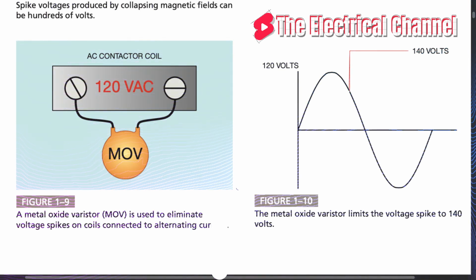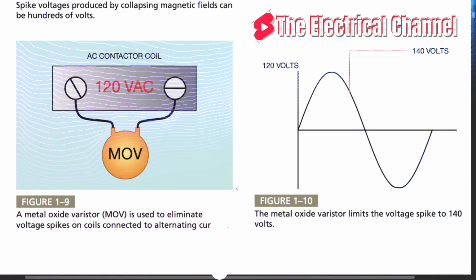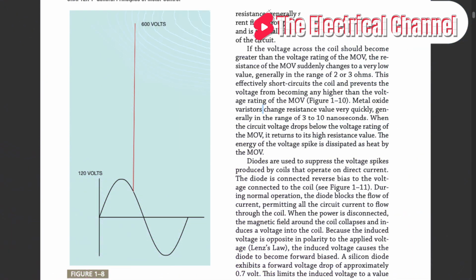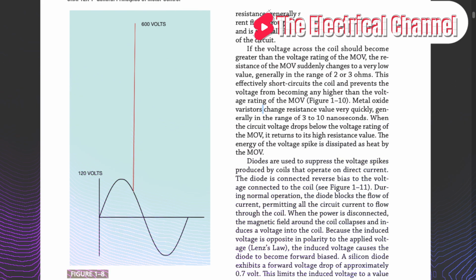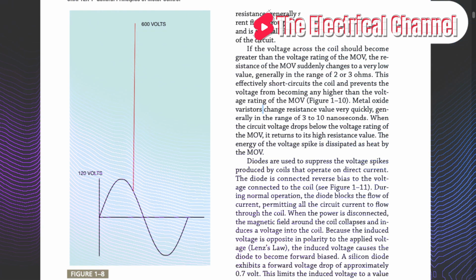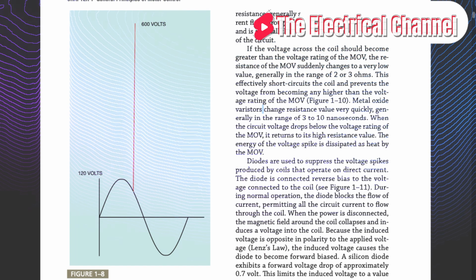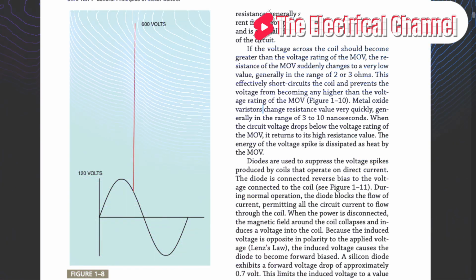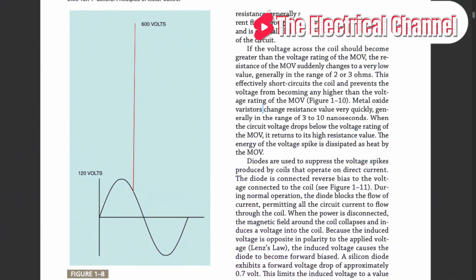Coils connected to alternating current often have a metal oxide varistor, or MOV, connected across the coil. Metal oxide varistors are voltage-sensitive resistors. They have the ability to change their resistance value in accord with the amount of voltage applied to them. The MOV has a voltage rating greater than that of the coil it is connected across. An MOV connected across a coil intended to operate at 120 volts, for example, has a rating of about 140 volts.